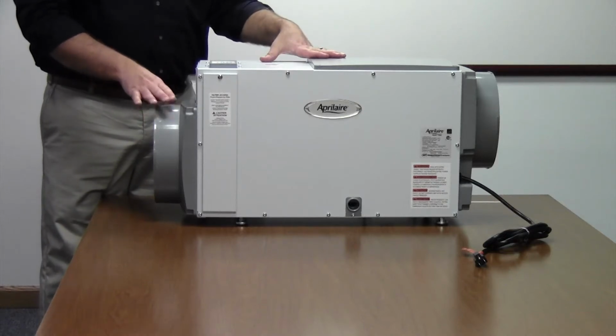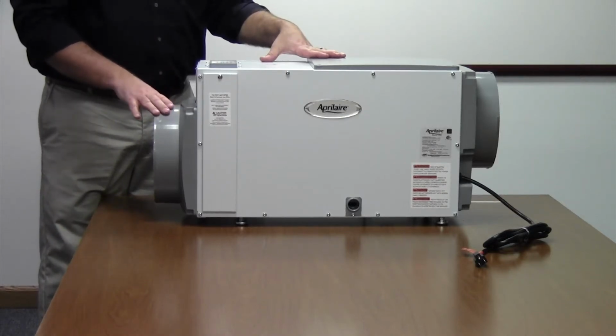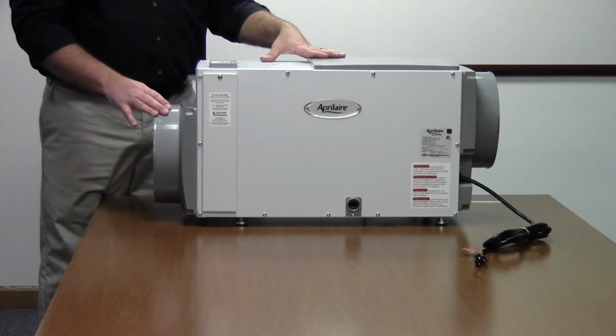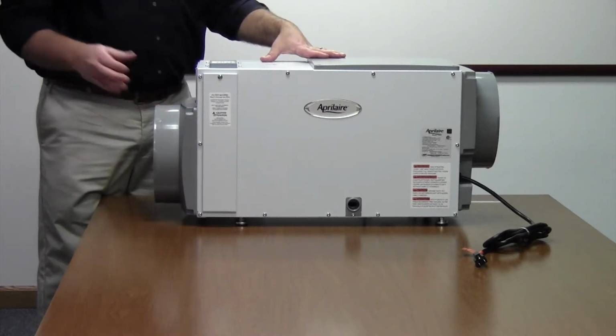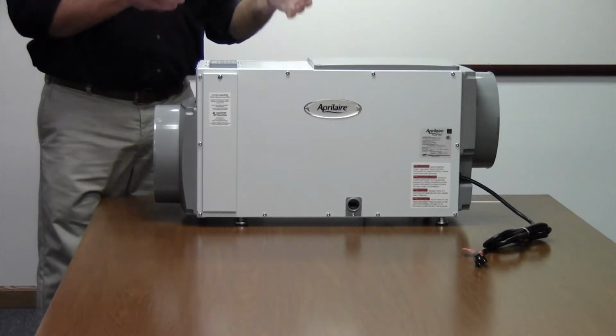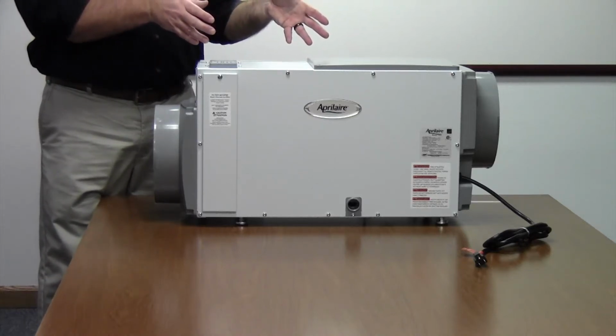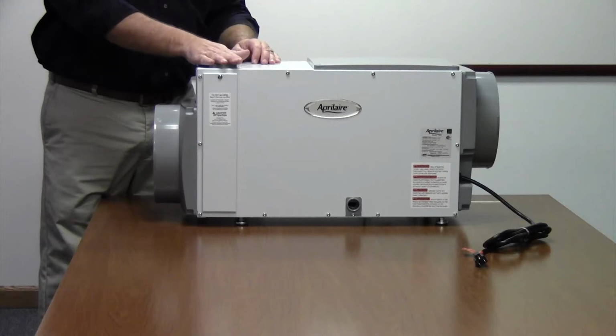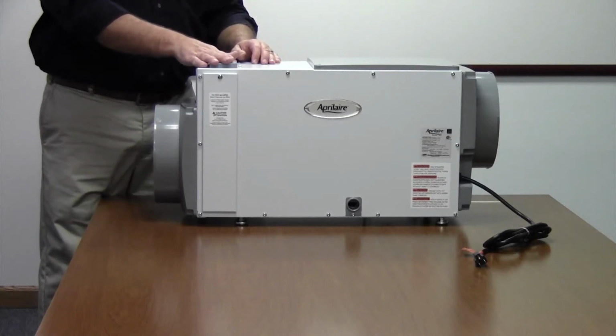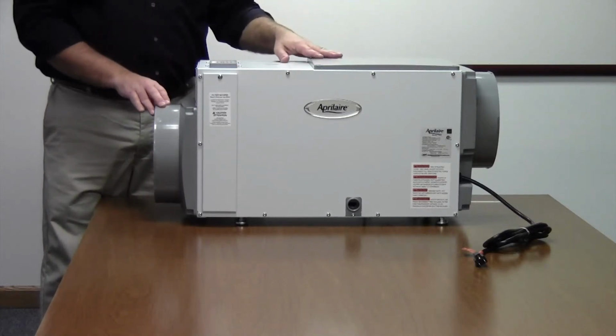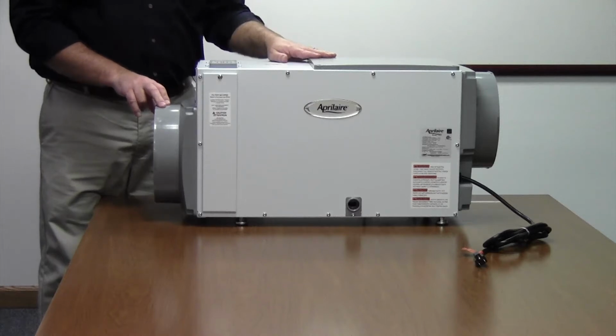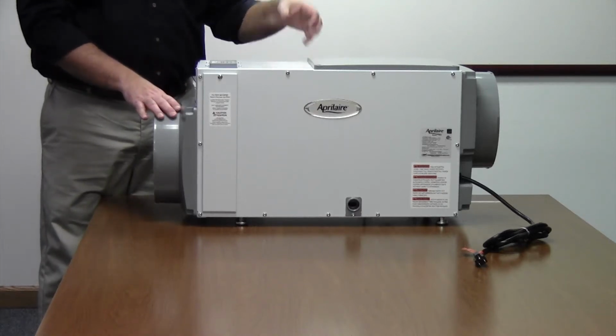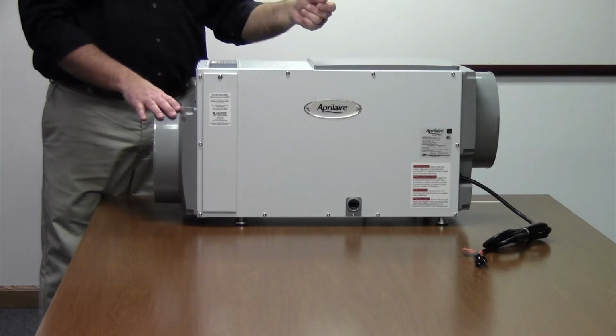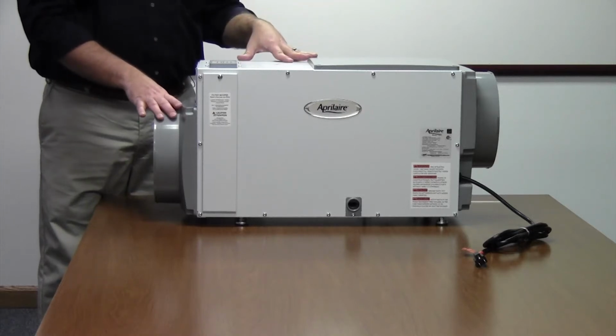These units are designed to go against some static pressure, but we do recommend that you duct it return to return, that you pull air from the return upstream and discharge the air downstream near the HVAC equipment. We're also going to wire in the fan circuit, and we'll talk about that later. But we do recommend return to return is our best application. You can pull air from the return and discharge into the supply duct as well, but we want to stay under 4/10 of an inch of static pressure when doing that.